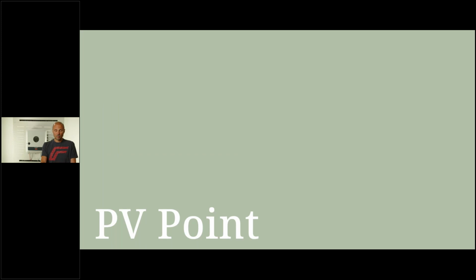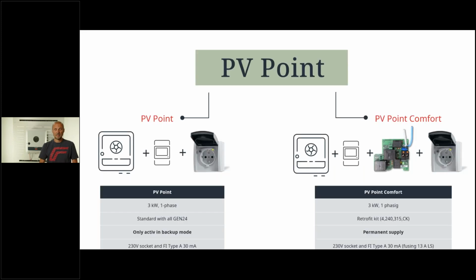So now to more details about the PV point. In the PV point, we also have two solutions. The PV point standard is integrated in all inverters, with just a socket. This PV point is only active in backup power mode. You need just the 230 volt sockets and the RCD type A, 30 milliamps.